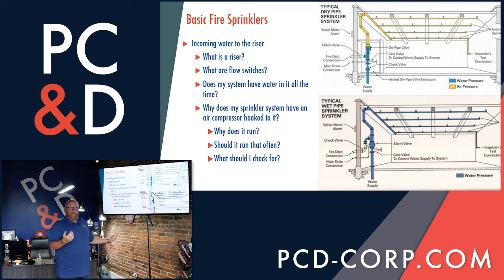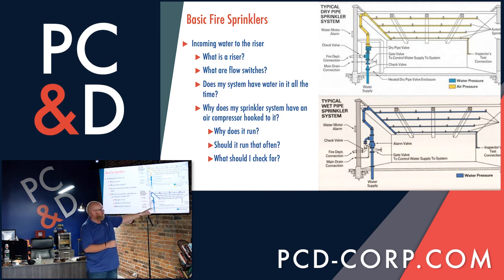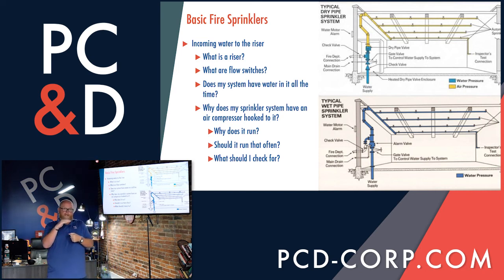So you might think, well, how does it know if I have a head that goes off? Once the head trips, you also have in these risers on both systems what's known as a flow switch. So as soon as that water moves to go toward a head, whether it's in a wet system, which always has water there but no water flowing, or whether it's in a dry system, as soon as that head trips and water starts to move, you have a flow switch inside that riser. When it moves, it rises just a little, functioning similar to a light switch or a toggle switch. As soon as that switch moves, it closes a set of points that then sends a signal back to your fire alarm that the sprinkler system has engaged. So that's a little bit on how the two systems, the sprinkler system, both wet and dry, communicate back to the fire alarm system.